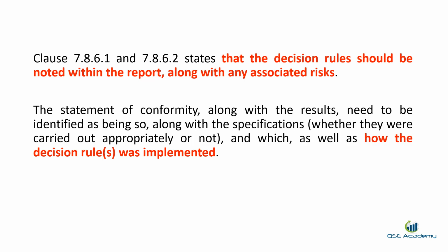The decision rules should be noted within the report, along with any associated risks. The statement of conformity, along with the results, needs to be identified as such, along with the specifications, whether they were carried out appropriately or not, as well as how the decision rule was implemented.